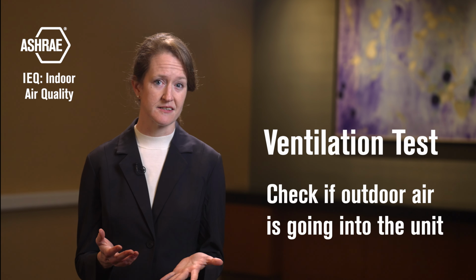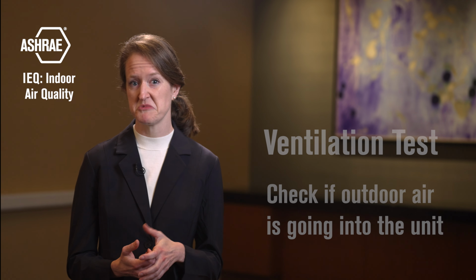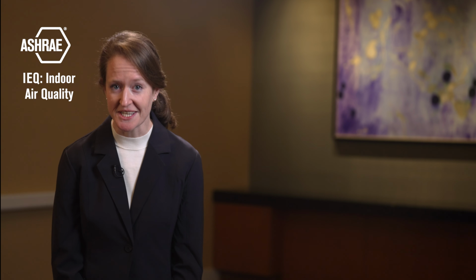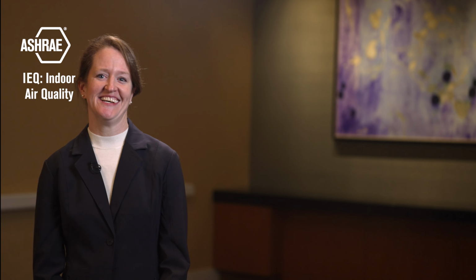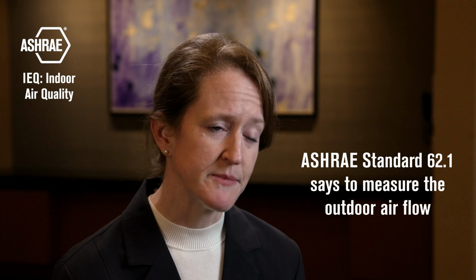For simplicity, we're not measuring the amount of airflow, just performing a yes-no test. I've seen units that didn't provide outdoor air for weeks, months, even years. This test can find the worst-case ventilation scenario of zero outdoor air. At some point, you will want to measure the outdoor airflow to ensure it's the right amount for the space. ASHRAE Standard 62.1, which sets minimum IAQ requirements, says to do this every 5 years.